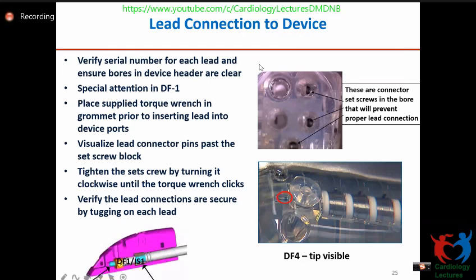For lead connection to the device, this is very important because ICD leads usually use the DF1 connection. You have 3 pins; for a dual chamber or CRT-D device, you have 4 to 5 holes. So make sure you put the pins in the right holes.